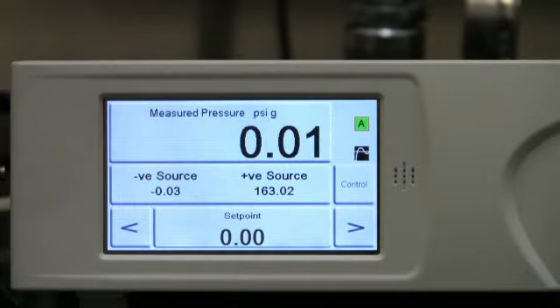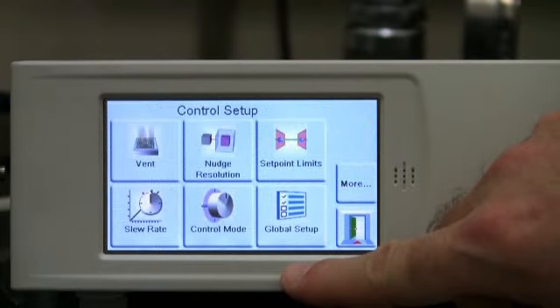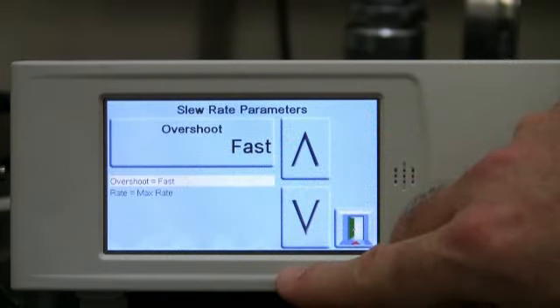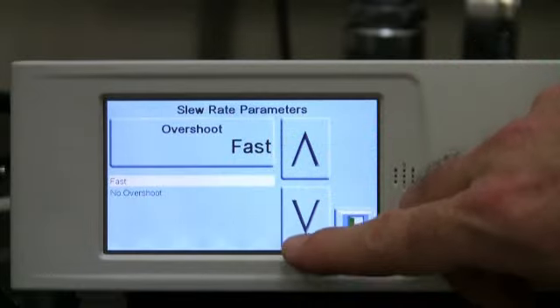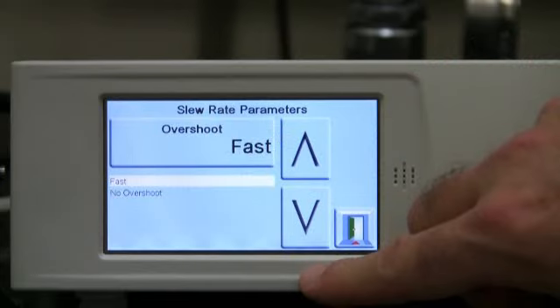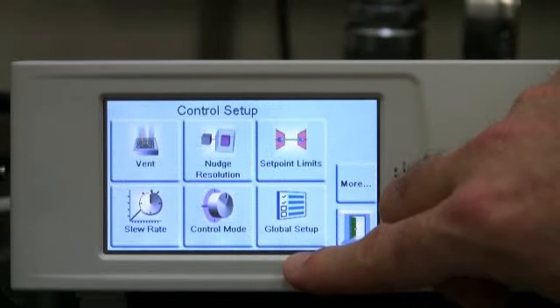PACE5000 allows you to change the control parameters to either maximize speed or, for high precision requirements, control to the set point with no overshoot. For this calibration run, we will select Fast.